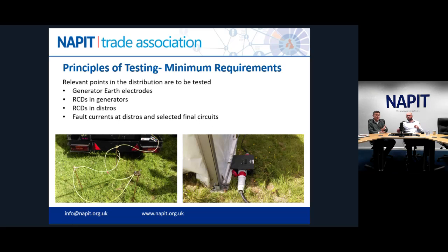With a temporary supply, they're often running off generators, and we'll touch on the new IET guidance on this in a minute. But the key thing is the generator earth electrode has to be of a low enough resistance to enable the output device on the generator to work if there's a fault to earth. Now, if that was a 100 milliamp RCD, we only need a small current flowing to trip the RCD. So the earth electrode resistance can be quite high. But if you didn't have an RCD, then it would need to be much lower resistance to get enough current flowing. So we need to make sure that the earth electrodes are effective. Okay. So that does mean testing them.